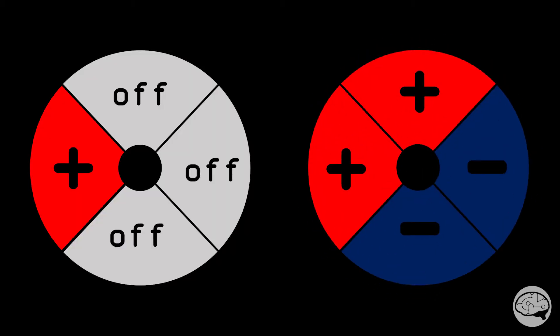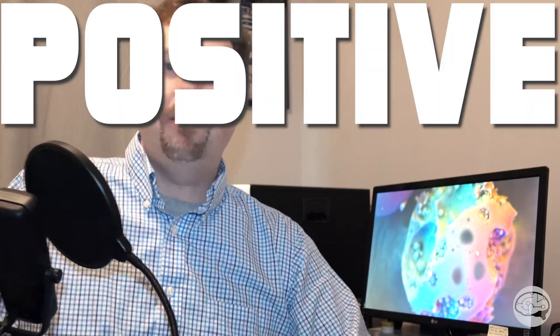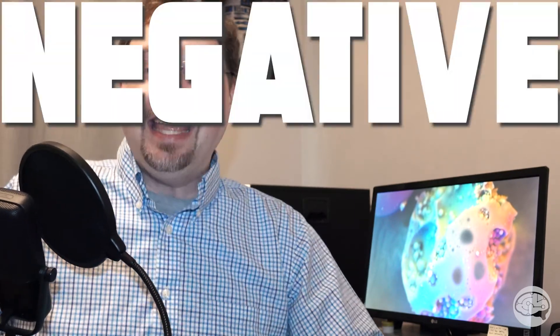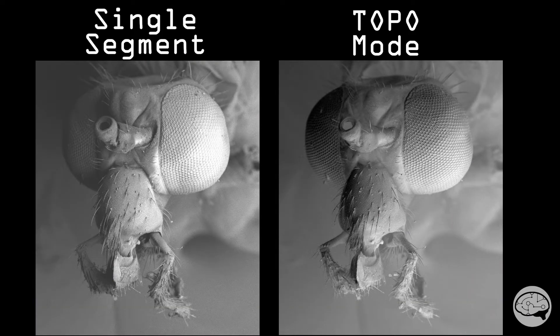First, instead of only collecting the signal from a single segment, we'll be using all four segments, but in different ways. In this case, we have A and D segments set to positive, and the B and C segments set to negative. So what does that mean, and why is that different from being off? Positive is additive. So if a segment is set to positive, signal from that segment will be added to the image. Basically, signal that hits that segment shows up as white. Negative is subtractive. That means that any signal that hits this segment will be subtracted from the image. Another way to think of it is that signal comes out as black in this condition. So why is this more desirable than the single segment collection? In this case, we're using all four segments and collecting a lot more signal. That's always great.